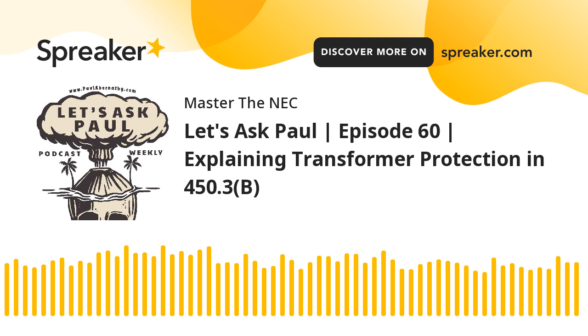So most people work it the other way. You could select the transformer, then do the math and see what the current rating is of it, and then have that say, okay, here's a 75 kVA. I think that's what I've got. In fact, if I looked at a 75, which is the most common, I go, okay, what's the maximum size that I can handle from that transformer? Okay, because the rating is the rating.